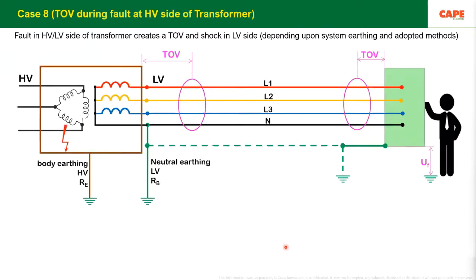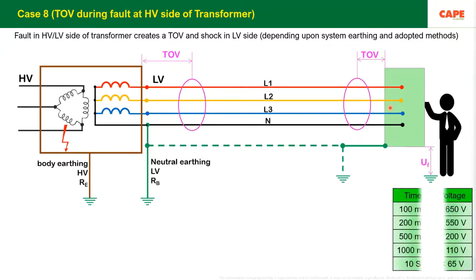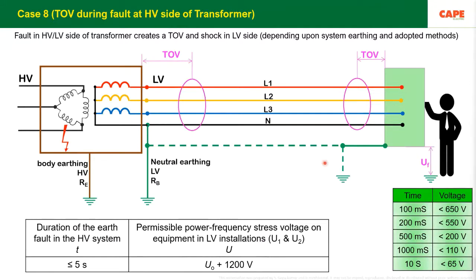Also, case number 8 is temporary overvoltage, meaning in case of a fault on a transformer. I'm showing you a transformer here on the left side. There is a fault on the transformer on the HT side. Whenever there is a fault on the HT side of a transformer, equipment in your building can burn. Temporary overvoltages up to 5 seconds can come into your building, which can create a shock hazard and a failure of apparatus.